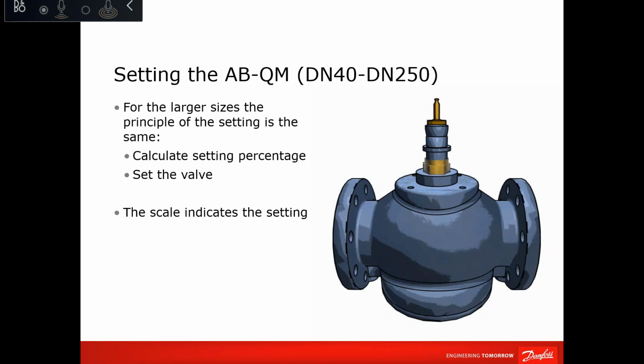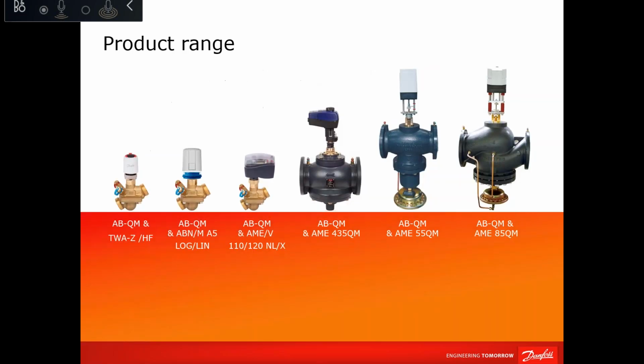of the setting. If you don't have the setting scale, someone broke it, or it was painted by mistake on site, you just calculate one turn as 10%. Fully close the valve, then open turn by turn, and you will get your setting. For the bigger sizes, DN125 and bigger, it's the same way. You need an Allen key. It's a small opening, and you want the scale down the side, but again, one turn is 5%.